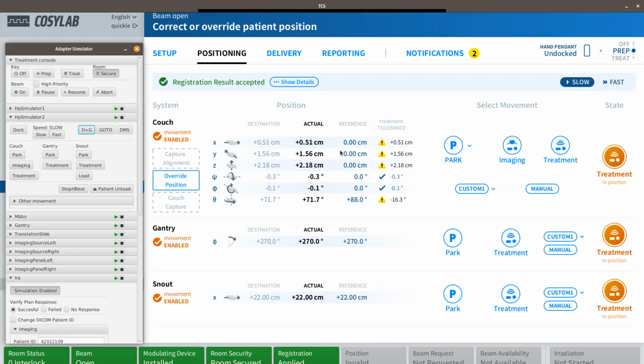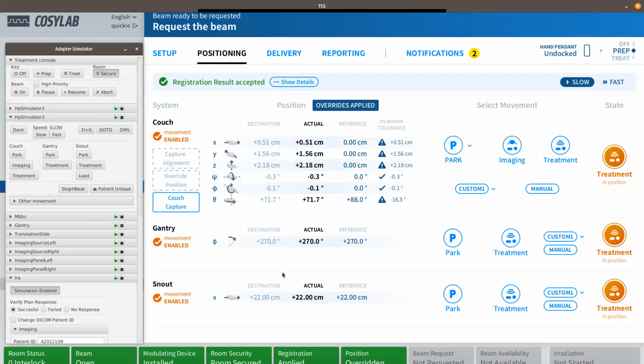In a real case, of course, the position is never completely the same as the ideal one. As you can see for the couch, there are certain offsets, and at this point we need to agree. The radiotherapist needs to look at this number and confirm that the result is still okay. This result is usually a consequence of image correction, image registration. So we will be happy with this result and confirm that everything is as it should be. Now, as you can see on the GUI, we are ready to request the beam.